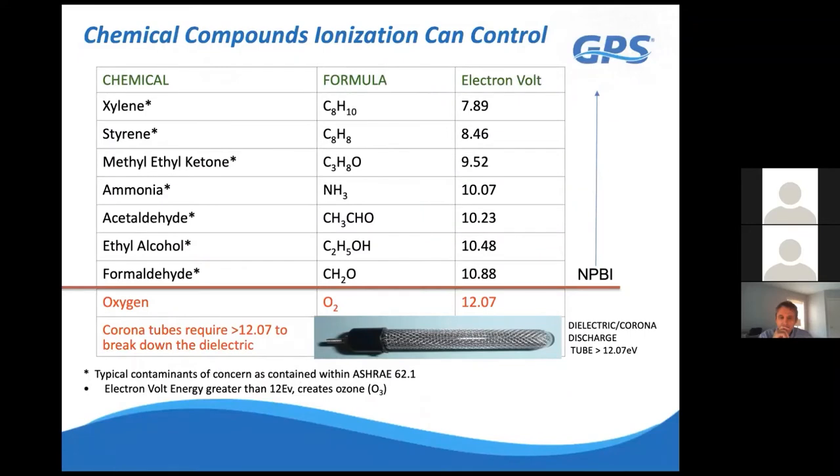The second benefit in NPBI is odor control. Every gas in the atmosphere has a specific electron volt potential. When you impart more energy into the airstream than a gas's electron volt potential, you oxidize and break it down, converting it back to what's already prevalent in the atmosphere—oxygen, nitrogen, water vapor, and carbon dioxide. Our technology operates at 12 electron volts, which is just below oxygen's threshold of 12.07 eV. Everything below 12 eV is broken down effectively; we stop there specifically to avoid ionizing oxygen and generating ozone.